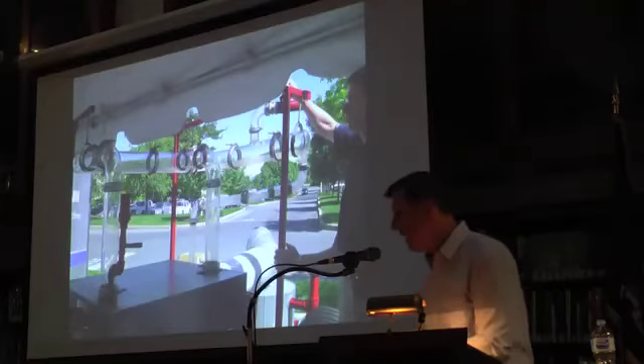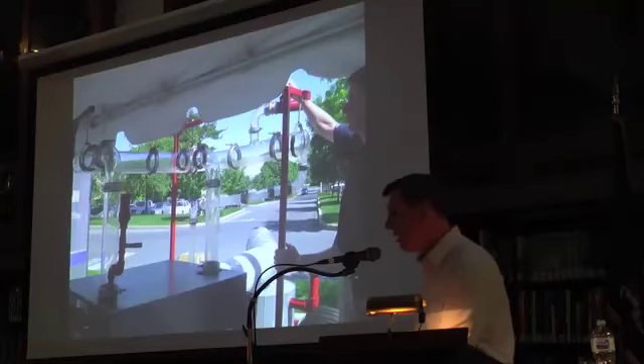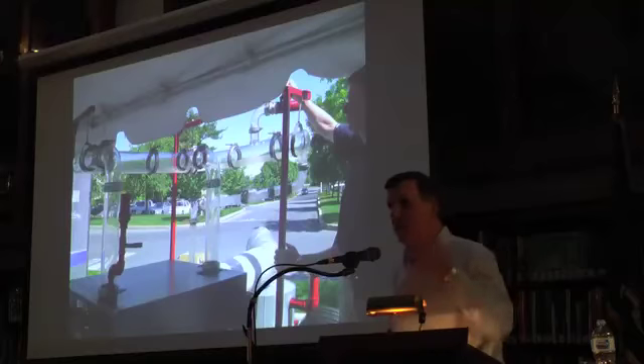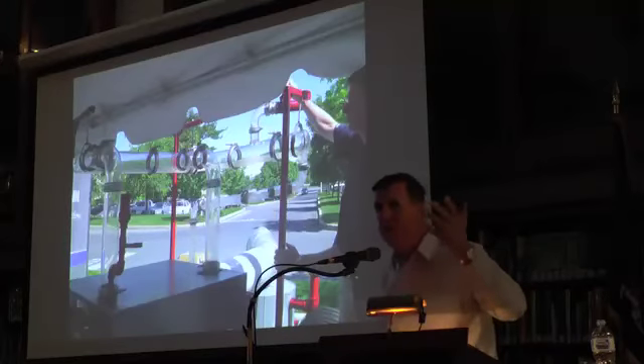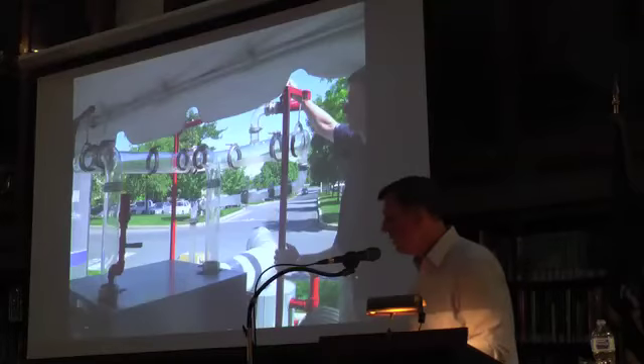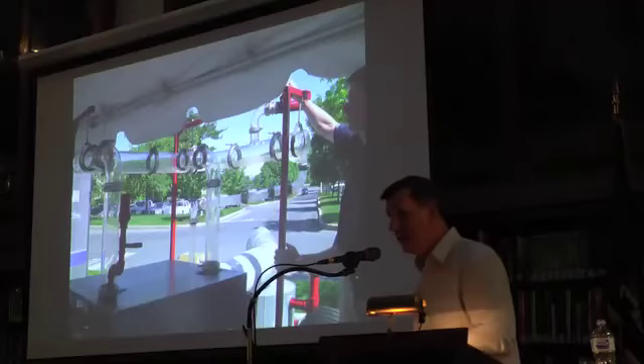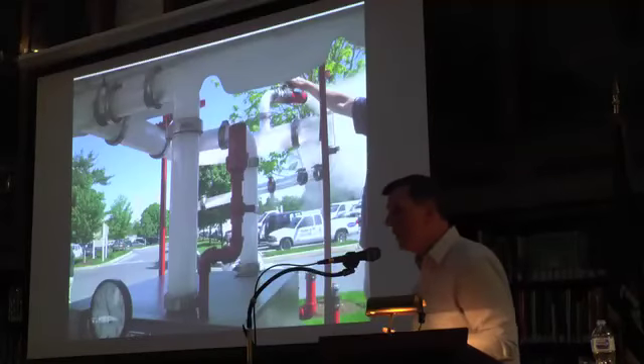So my buddy Mike here, he's got about 3 pounds of pressure on the boiler, and he's going to close that valve and show you the effect of quick opening motorized valves that a lot of people like to add to systems to try to zone the system. When he opens that valve and releases the pressure, it's like shaking up a bottle of Coke and popping a lid. Suddenly, all the water that's in that boiler winds up out in the parking lot.